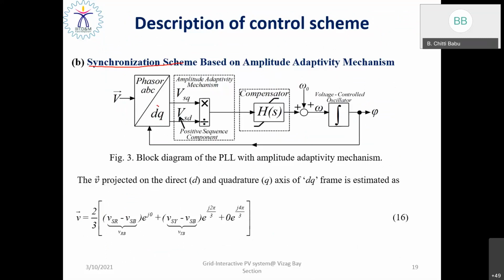The D-axis component is for active power and the Q-axis component is for reactive power. Even many researchers decompose for getting both the positive sequence as well as the negative sequence component, because the D-axis component basically represents the positive sequence component as far as the symmetrical components concepts are concerned, because the positive sequence component is very essential for active power control. The negative sequence component is very essential to reject the harmonics present in the grid current, right? So we use the positive and negative sequence.